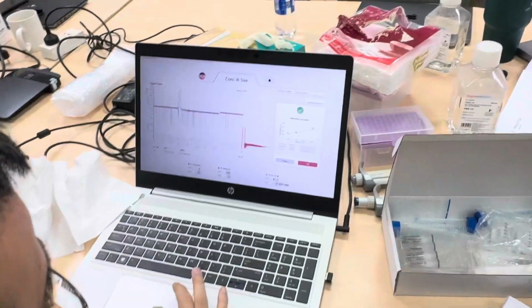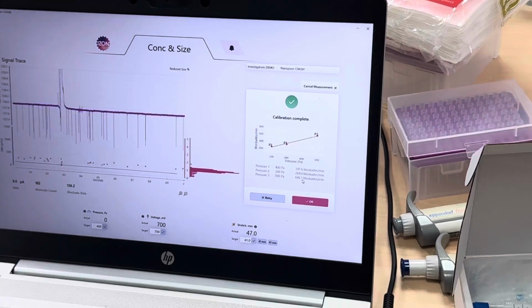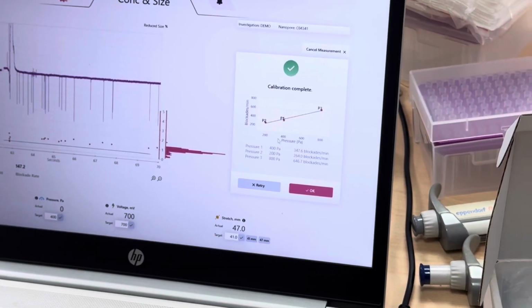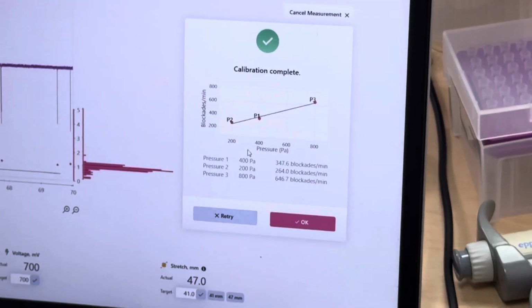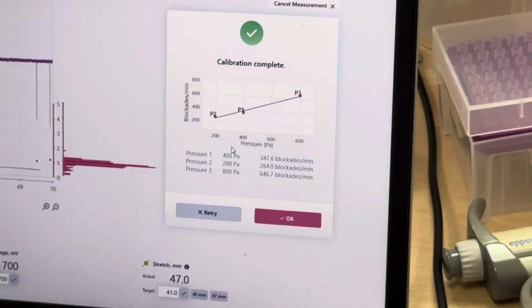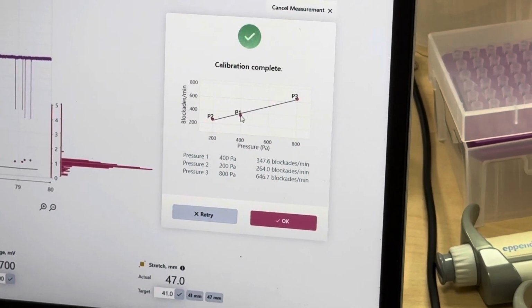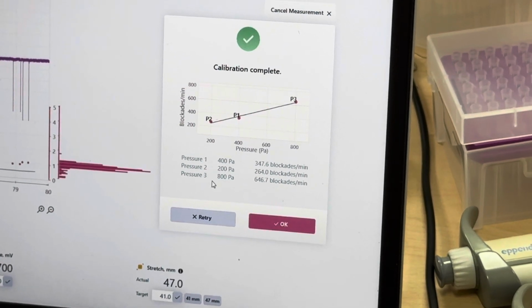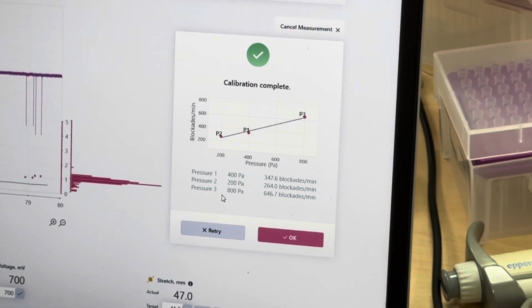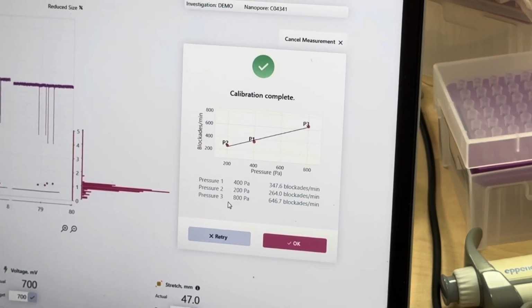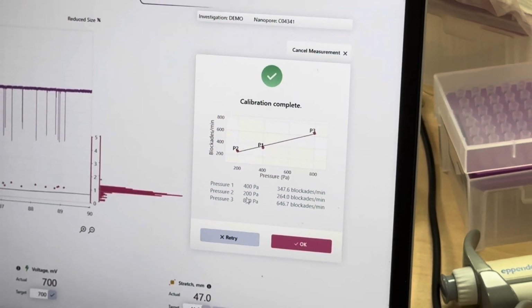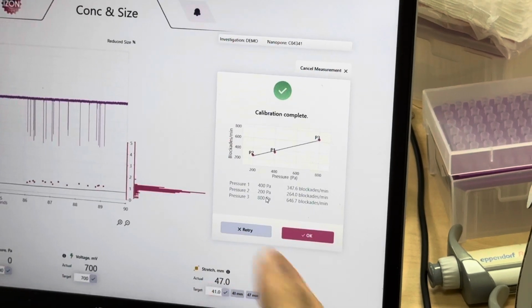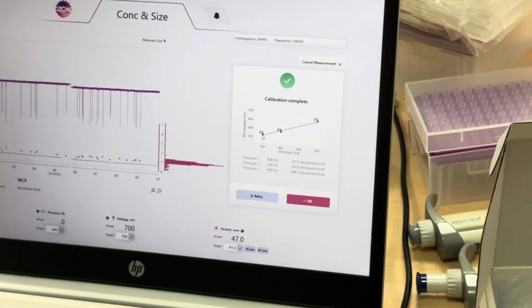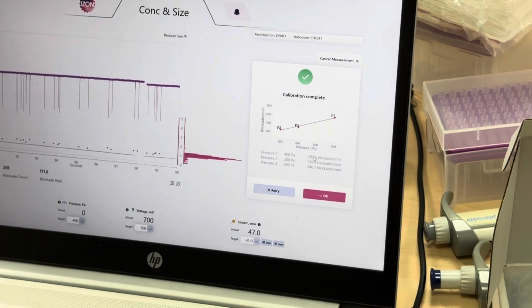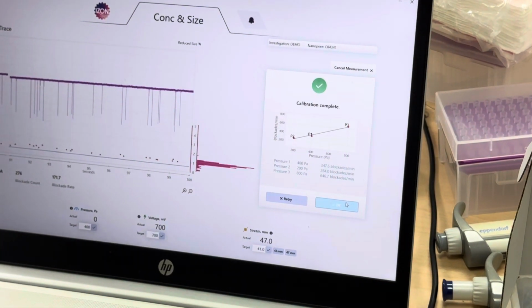And you see that this calibration has been done, so it just takes around 5 minutes. And then this is the QC map. We know that with a higher pressure, the flow rate should be higher, so it's linear. That's why we read 3 pressure readings. If we have too many samples, for example like 20, 30 samples a day, to save time, you just need to do 2 pressures. It's fine to save time, because the third one is just to confirm it's right. And you see that with the higher pressure, the flow rate is higher, which means calibration has been done.